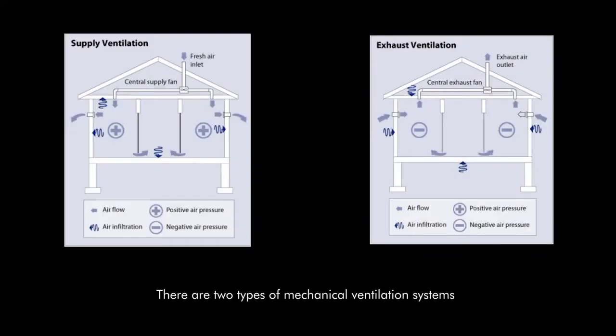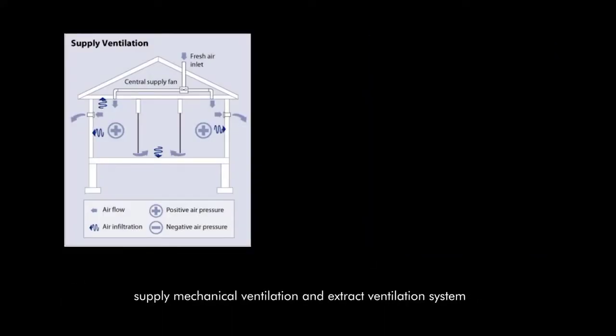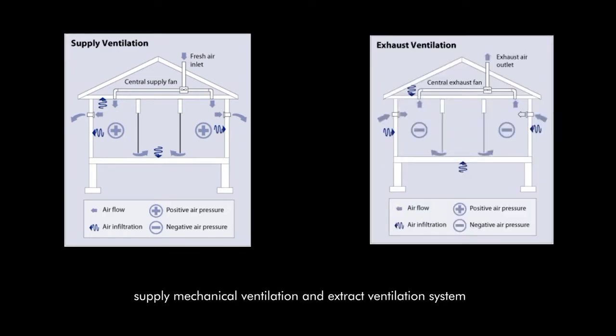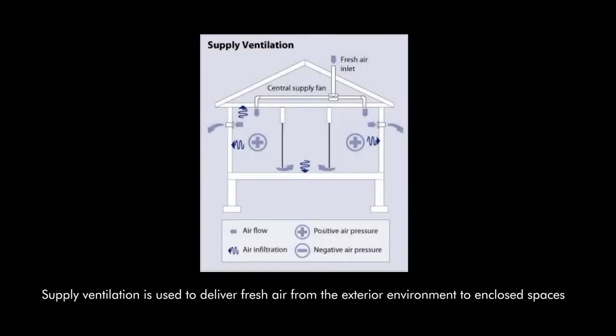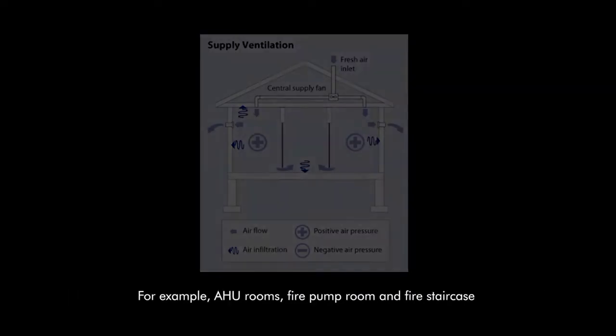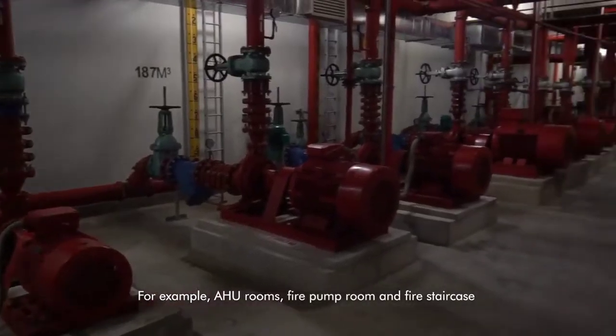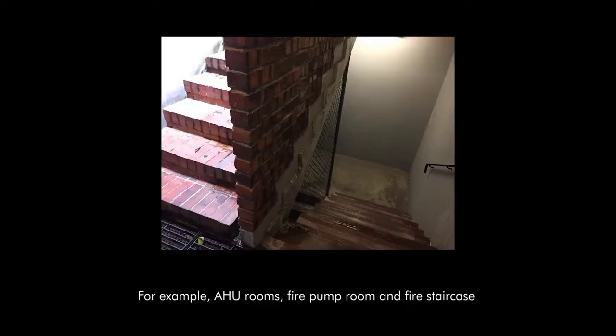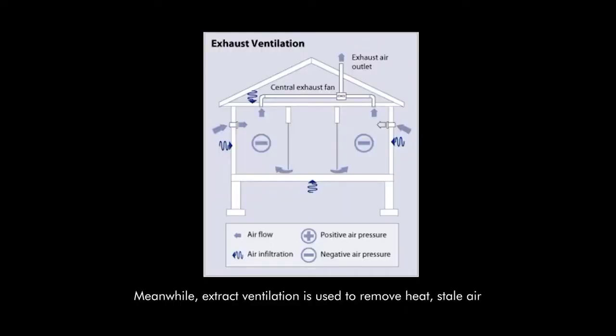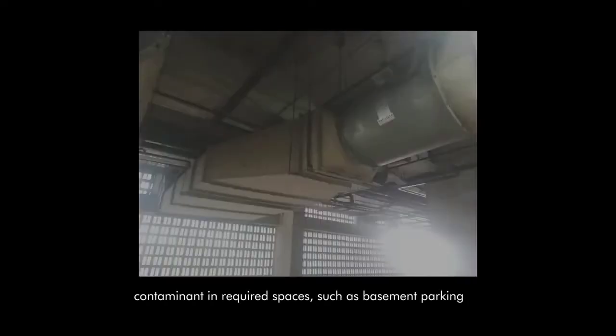There are 2 types of mechanical ventilation system: supply mechanical ventilation and extract ventilation system. Supply ventilation is used to deliver fresh air from the exterior environment to enclosed spaces, for example, AHU room, fire pump room, and fire staircase. Meanwhile, extract ventilation is used to remove heat, stale air, and contaminants in required spaces such as basement parking, lift room, and other utility rooms in basement.